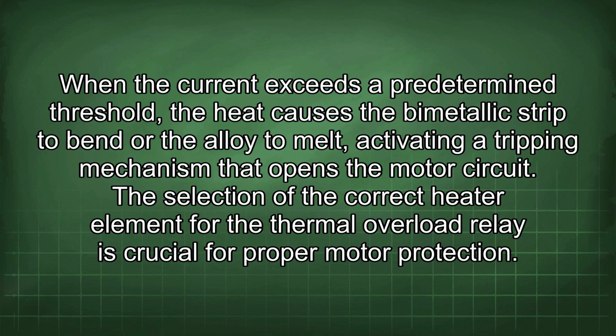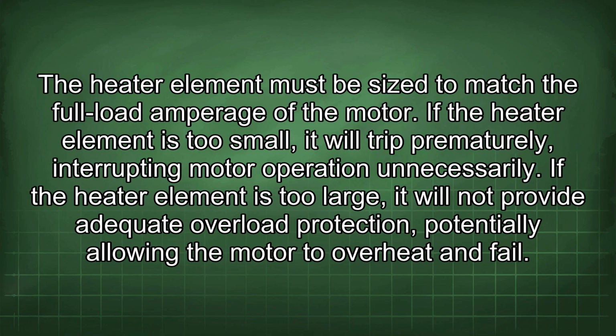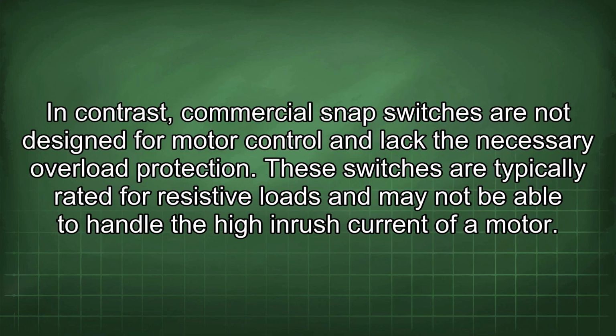The selection of the correct heater element for the thermal overload relay is crucial for proper motor protection. The heater element must be sized to match the full load amperage of the motor. If the heater element is too small, it will trip prematurely, interrupting motor operation unnecessarily. If the heater element is too large, it will not provide adequate overload protection, potentially allowing the motor to overheat and fail. In contrast, commercial snap switches are not designed for motor control and lack the necessary overload protection.